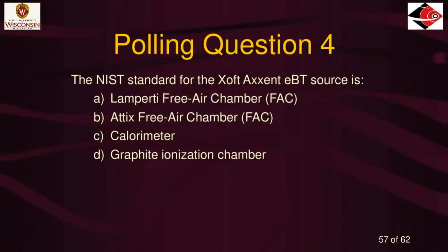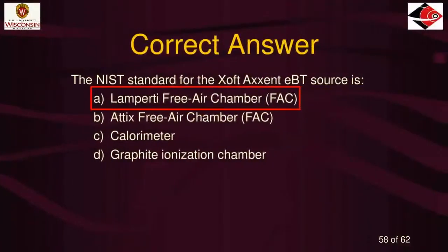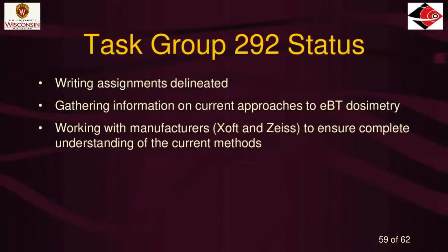The correct answer is A, the Lamperti free air chamber. Most everybody answered that, but several answered the Attix free air chamber — which is probably the most common free air chamber covered in textbooks for mammography energies. It's very similar to the Lamperti chamber but used for slightly different purposes for mammography X-ray beams, and it was not the one chosen for the Xoft project. A calorimeter is definitely not used — the energy is too low. The graphite ion chamber can't be used either because it has too thick a wall.